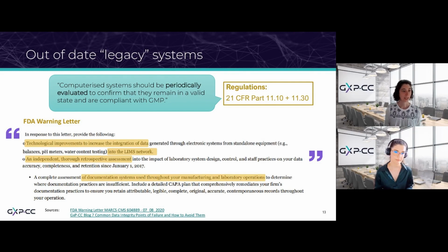In this case, the FDA requested technological improvements to increase the integration of data in the lab into the LIMS network. So this company did have a LIMS, but they weren't pulling that data in from devices like balances and pH meters to really leverage all of what you can get out of the LIMS.